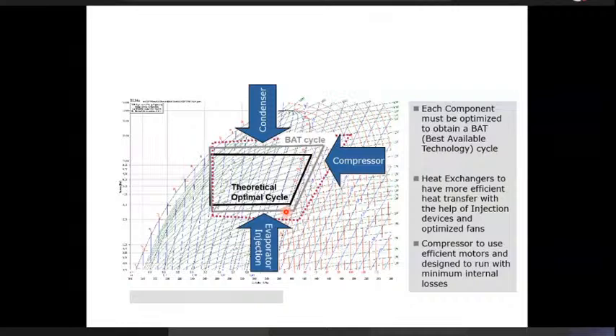So these are the important parameters as far as this particular slide is concerned. The chart I'm using here is an R134a chart, and that is just for illustration purposes. This entire set of comments that I have shared with you will apply for any refrigerant that you use. If we were to use a rotary compressor, then the heat rejection of the motor happens in the discharge gas. So then we will have some change in this part of the cycle.